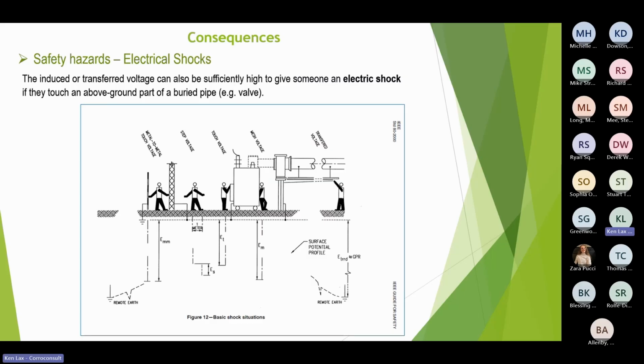You can see the dependence upon the surface potential profile and the step distance and the touch separation distances. It's an art in itself, designing all these things to make sure people don't get electric shocks. And you might think to yourself, well, it doesn't affect me because I'm working with a buried pipeline. Well, unfortunately, when you build the pipeline, the cathodic protection guy has a cable brazed onto the pipe and brought up to the surface at a test post.